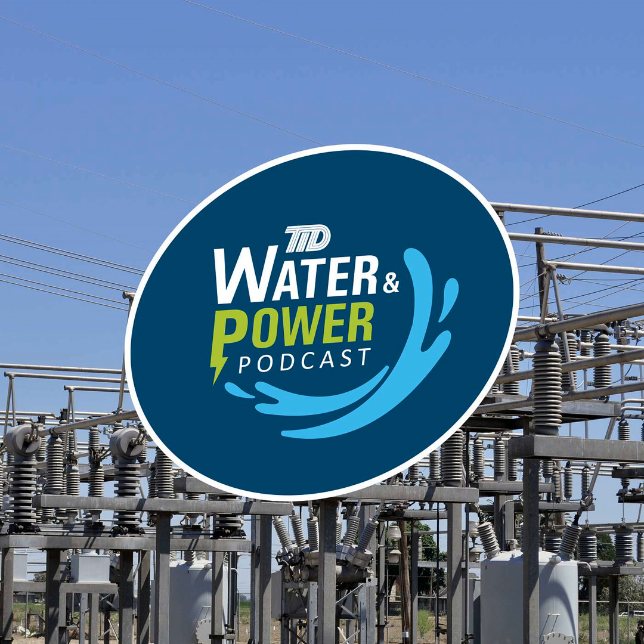With protective relays, depending on the type, they're looking for those cues I mentioned. We do some protection across communications, where a relay on one side of the line and a relay on the other side talk to each other, making sure they're seeing the same thing. If they're not, that causes an interruption for protection purposes.